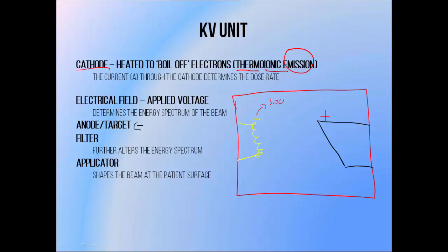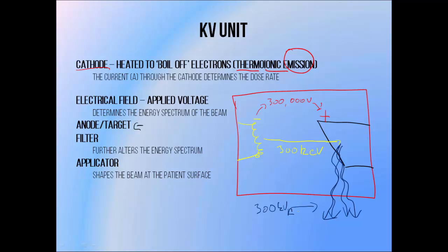If we apply a voltage of 300,000 volts between the two, the electrons will gain an energy of 300 kiloelectron volts, since one electron volt is the energy that an electron gains when it is accelerated using one volt. This means that when the electron beam strikes the target and undergoes the bremsstrahlung interaction, it will produce a photon beam with a maximum energy of 300 keV. So we say that the beam has a KVP, or peak kilovoltage, of 300.